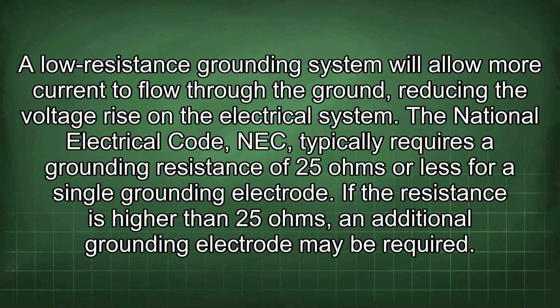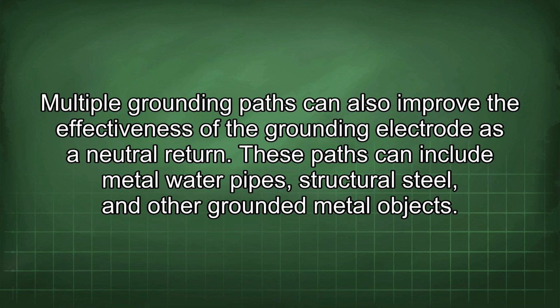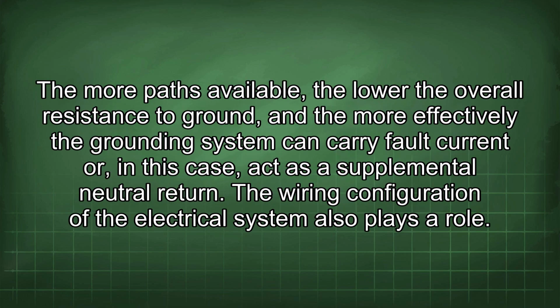A low resistance grounding system will allow more current to flow through the ground, reducing the voltage rise in the electrical system. The National Electrical Code, NEC, typically requires a grounding resistance of 25 ohms or less for a single grounding electrode. If the resistance is higher than 25 ohms, an additional grounding electrode may be required. Multiple grounding paths can also improve the effectiveness of the grounding electrode as a neutral return. These paths can include metal water pipes, structural steel, and other grounded metal objects. The more paths available, the lower the overall resistance to ground, and the more effectively the grounding system can carry fault current or, in this case, act as a supplemental neutral return.